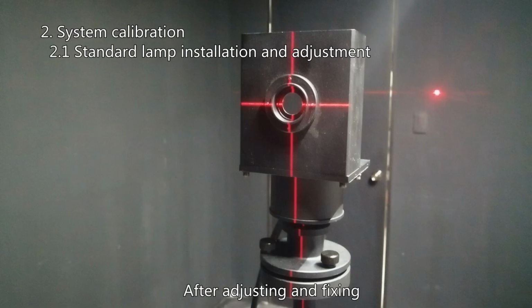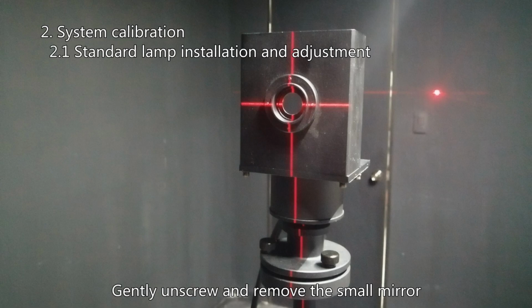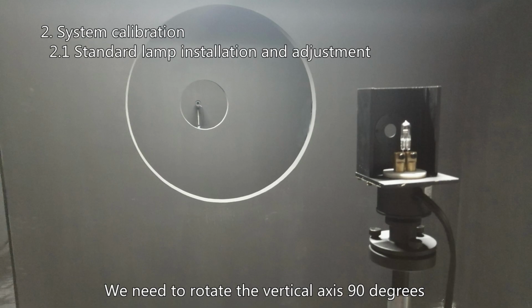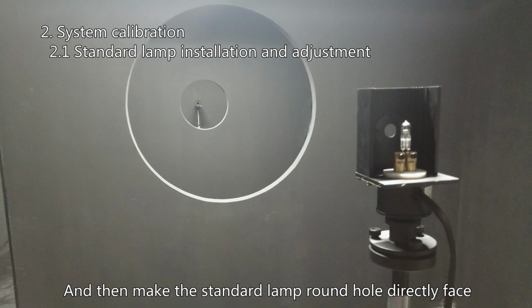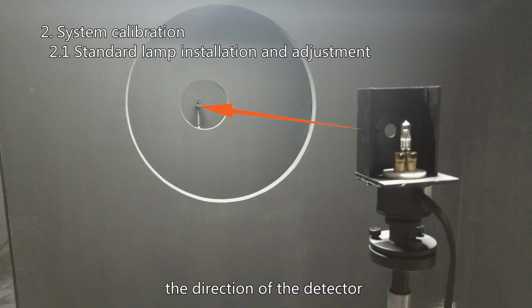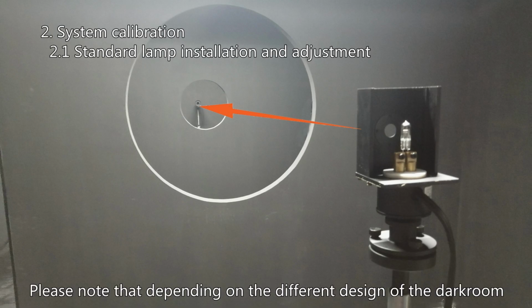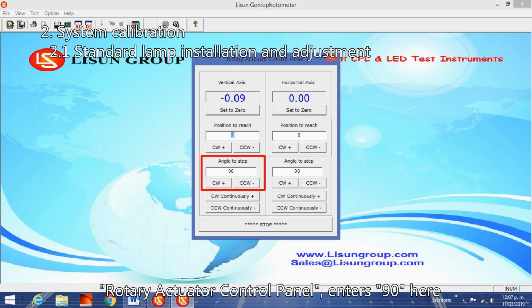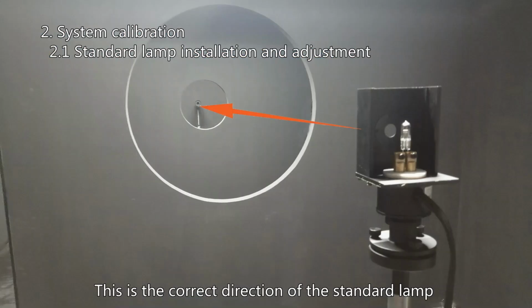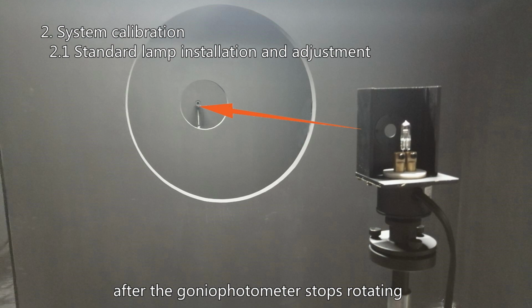After adjusting and fixing, gently unscrew and remove the small mirror. Turn off the cross laser. We need to rotate the vertical axis 90 degrees, and then make the standard lamp round hole directly face the direction of the detector. Please note that depending on the different design of the darkroom, it may need to rotate clockwise or counterclockwise. Rotary actuator control panel enters 90 here. Choose clockwise or counterclockwise according to the actual situation. This is the correct direction of the standard lamp after the goniophotometer stops rotating.